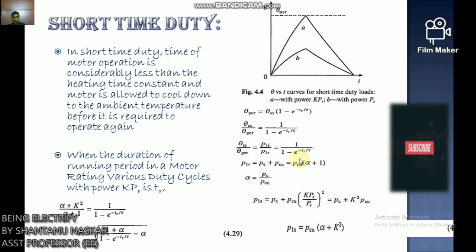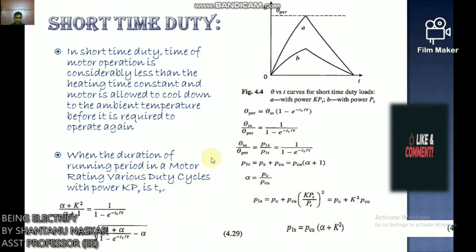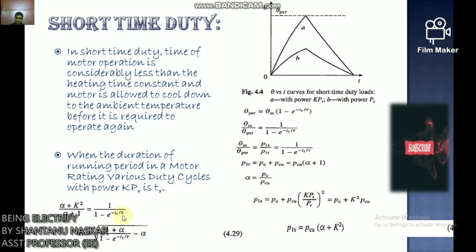Where PC is the load-independent constant loss and PCU is the load-dependent loss, and α = PC / PCU. From these equations, (α + K²) / (α + 1) can be used to calculate the overloading factor K. When constant and copper losses are not known separately, total loss is assumed proportional to power squared, setting α = 0. K is also subject to constraints imposed by maximum allowable current for DC motors and breakdown torque for induction and synchronous motors.